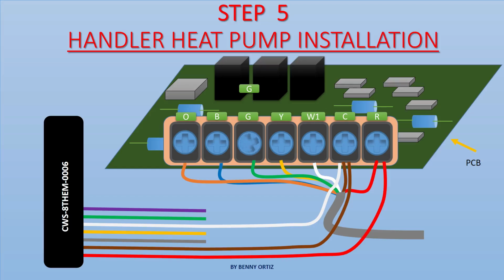Loosen G terminal. Release the green wire from the G terminal. Note that this green wire is actually coming from the thermostat wire bundle. Connect HVAC chip gray wire to this green wire with a twist and wire nut. Connect green wire from HVAC chip to G terminal and retighten. Note, if there is no purple wire on the HVAC chip, your installation is now complete.